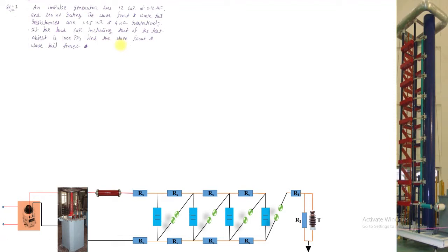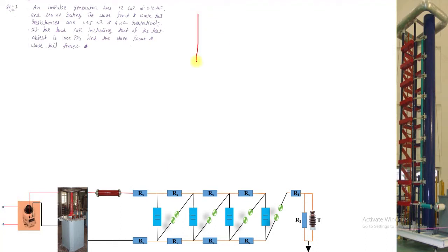During the theory session, we have seen that the impulse voltage wave is classified by its polarity, peak magnitude and time intervals. The time intervals are further classified into two parts. One is the wavefront time, which denotes that the wave attains the peak magnitude in a very short duration. Let me draw to understand it more. So here this rising stage indicates the wavefront portion and this reducing rate determines the wavetail time.